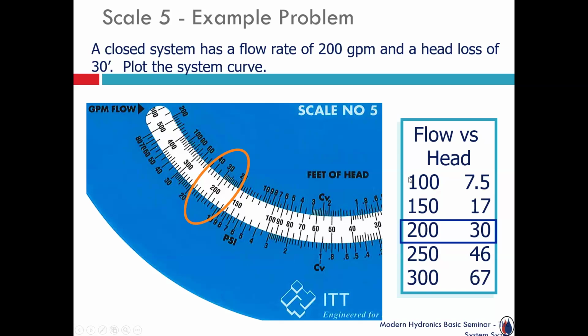You've calculated it. To build a system curve, you can really just arbitrarily pick other flow rates. And what you do is, once you're on scale 5, line up the two known conditions, and then 100 GPM, read straight up, 7.5. 150 gallons a minute, just about what? 17, 10, 15, 16, 17 feet of head.